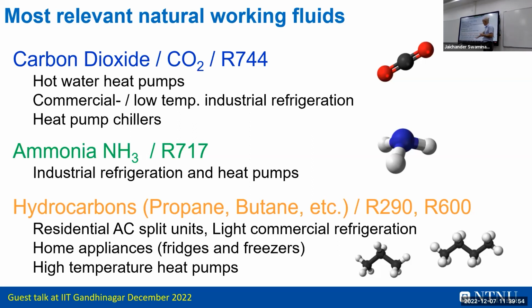Compared to a conventional system that just condenses, where maybe you don't need the heat so you reject it, you don't need to go very high in pressure to reject heat to the ambient, and you can make comfort cooling. Or vice versa, reject it straight into the room at 25-30 degrees, which gives you heat, and you can do this with condensing inside the heat exchanger. So it's a bit about the process, but one doesn't fit all. We need to design the architecture for each system according to the properties of the fluid and adapt it to find what is best.